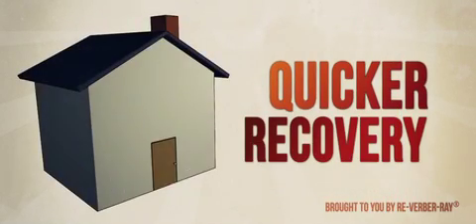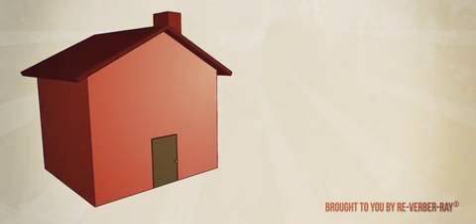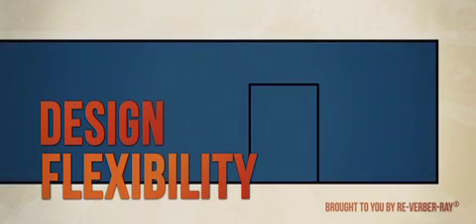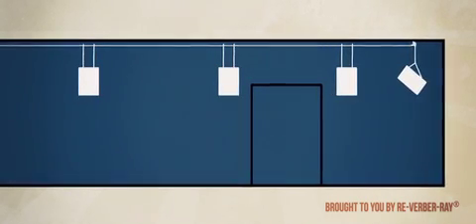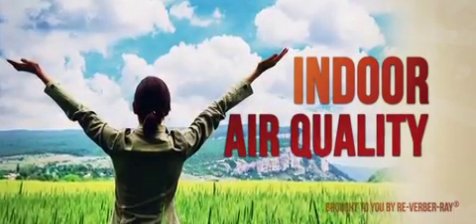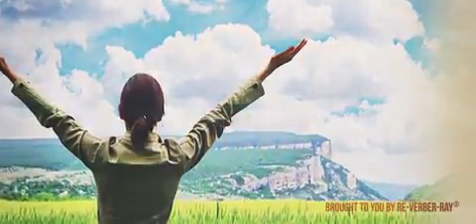Quicker recovery: stored infrared energy provides a quick and effective solution to areas subject to periodic high-air changes. Design flexibility: infrared heaters can be located where heat is needed most, rather than wasting energy by heating unoccupied areas. Indoor air quality: since infrared heaters do not rely on air currents to transfer heat, the circulation of dust and debris is minimized.